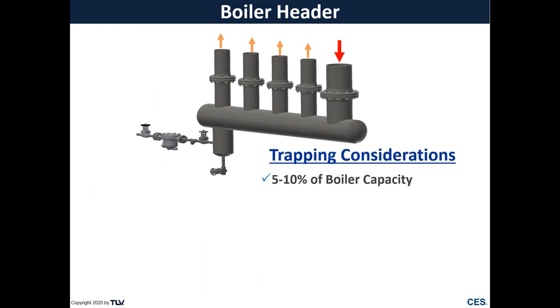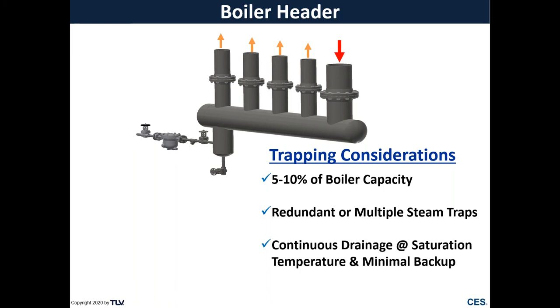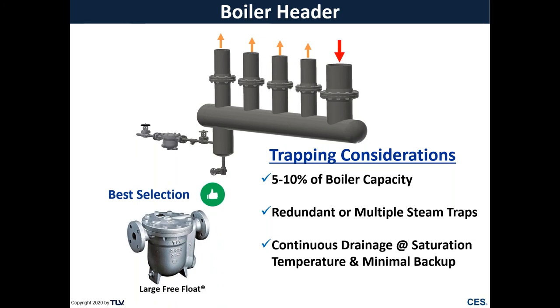So in our trapping considerations here, we're generally going to want to size this trap for about 5 to 10% of our boiler capacity, which is going to result in a large trap. And we may even want redundant or multiple steam traps on this application to provide sufficient drainage. We're going to want something that is going to continually drain with minimal backup. So our best selection here is going to be a large mechanical trap, such as a free float.